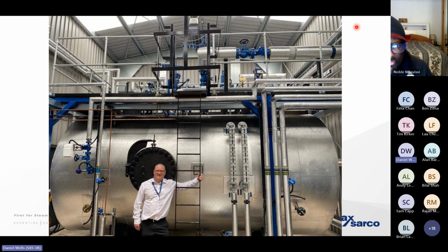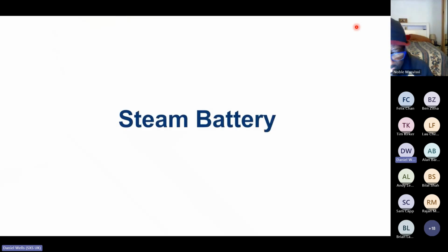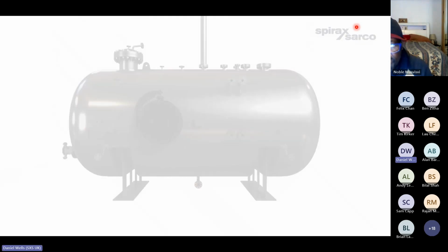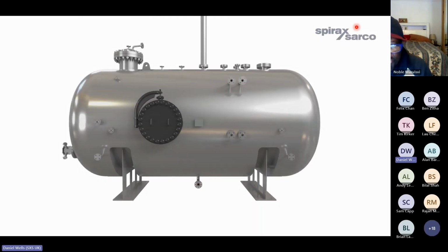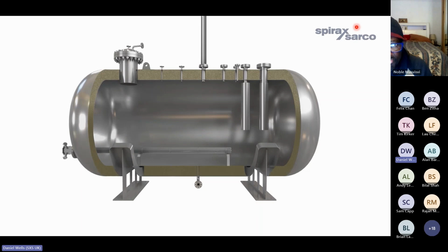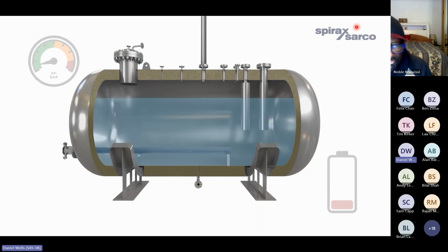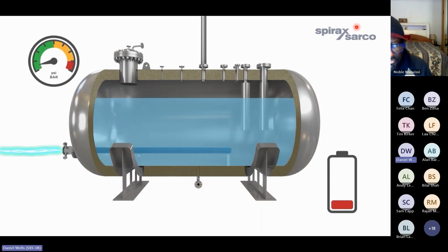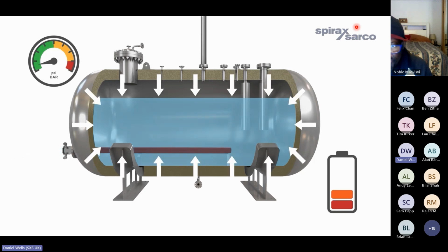It's got that series of electrical elements that generate steam slowly, generate hot water slowly, until such time that the vessel needs to be depressurized to produce steam. So it's technology that the vast majority of boiler operators would be very, very comfortable and familiar with. So again, just a little animation to bring it to life off the page. That pressurized vessel, electrical elements running through it, we slowly elevate the pressure and the temperature.